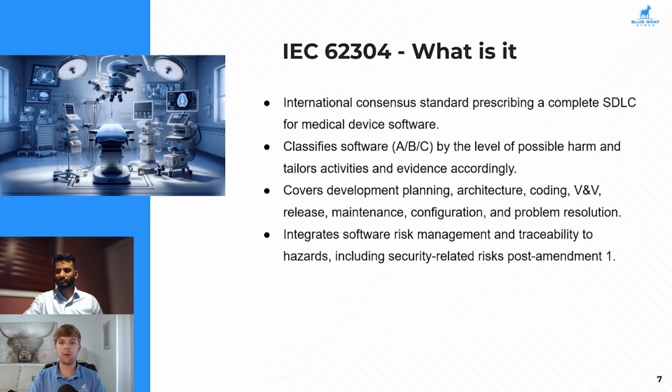All right. Next, we're going to go into IEC 62304. This is a standard where we're talking about that secure software development lifecycle for medical device software. This is also where we get into some of the distinctions between class A, B, C or class 1, 2, 3 in the FDA terminology by that level of harm, and then what activities we need to prepare specifically for different classes of device. This all goes back to that risk-based approach.